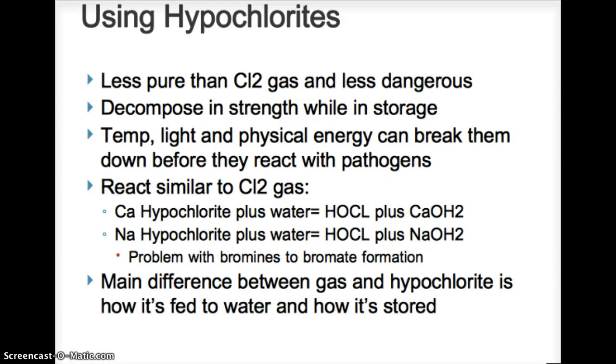Okay, so using hypochlorites, this would be basically the solid or liquid form. They are less pure than chlorine gas and less dangerous. They decompose in strength while in storage. The temperature, light, and physical energy can break them down before they react with pathogens.